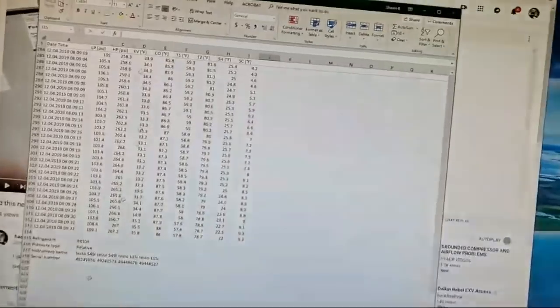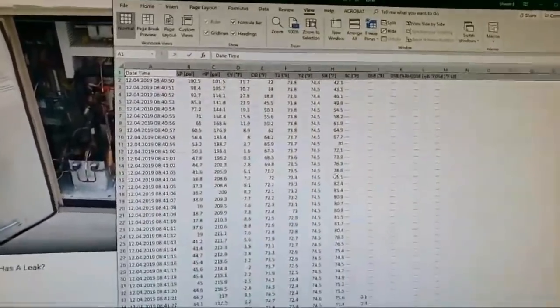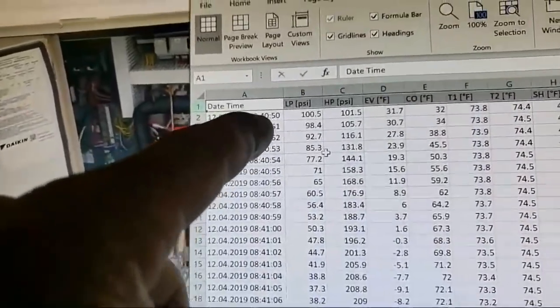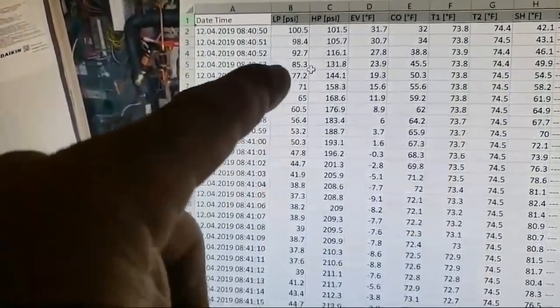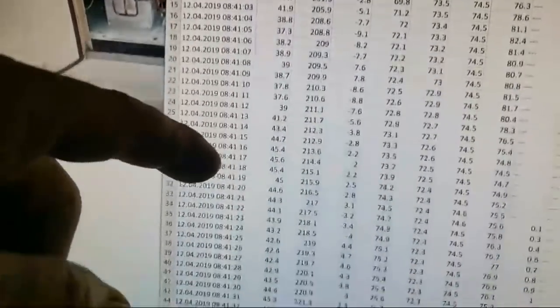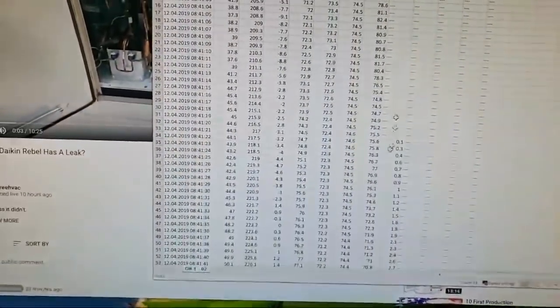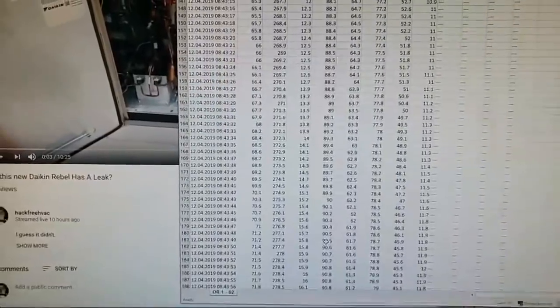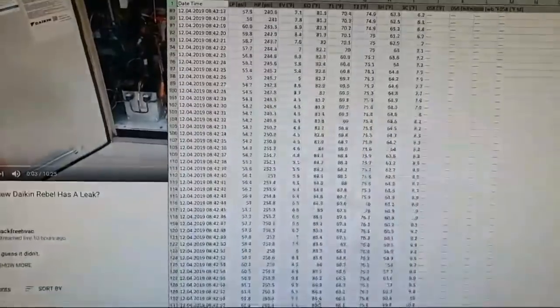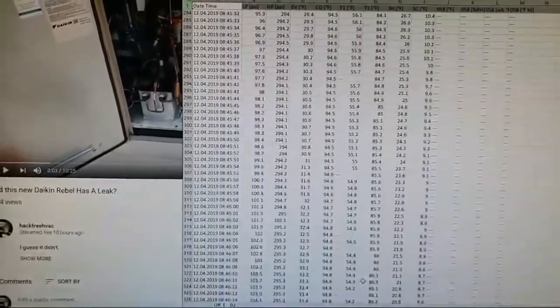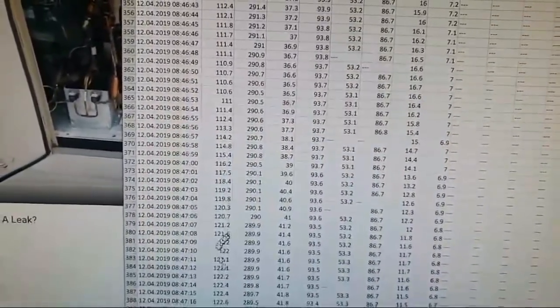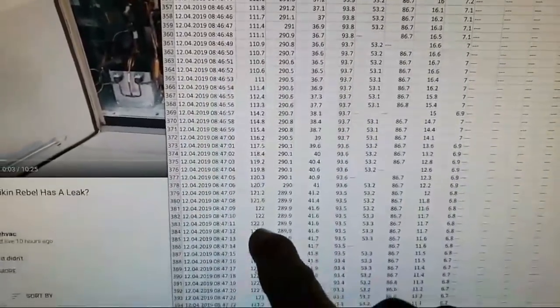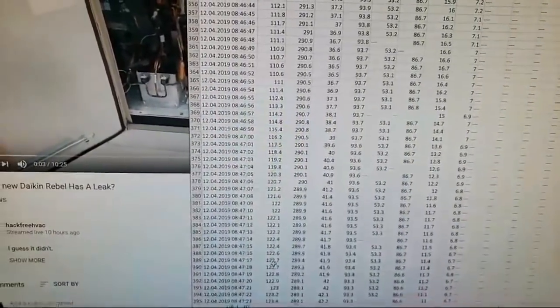And here's the thing. So at 804 it kicks on and I'm equalized, right? 190 PSI of R410. It goes and immediately just shoots down to 12 PSI in the suction. I say immediately, but you see it started at 23 seconds. And so 30 seconds later at 54 seconds, after 30 seconds, you shouldn't be still going down on suction, I would think. So I'm like, whoa, this sucker's probably lower charge. Look at that. It was like 0.4 degrees of subcooling, right? Because at the top there's a subcooling superheat. Superheat was 102, 208 over 12 point, 208 discharge, 12.7 suction.